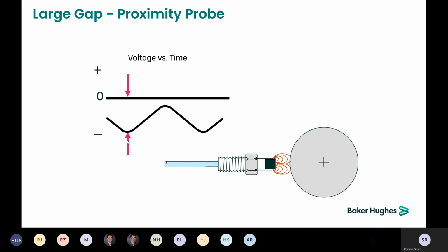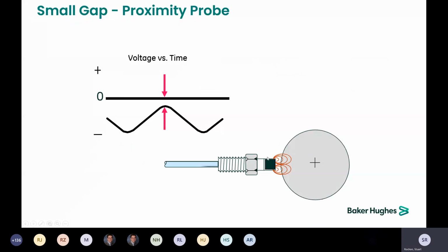So here, the probe is far away from the shaft material. With an 8 millimeter proximeter, you're generally going to see something in the 19 to 21 volts negative if there is no material in the field. As you get closer, and the shaft gets right up against the probe tip, you'll see it go down to about a negative 0.65.